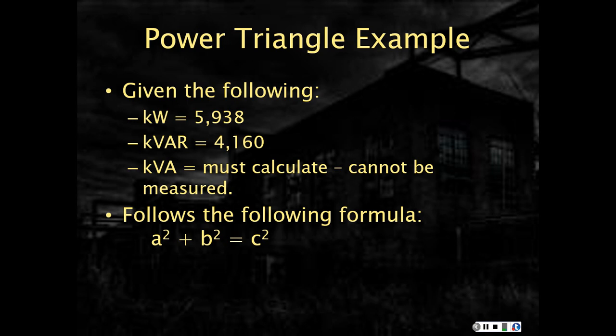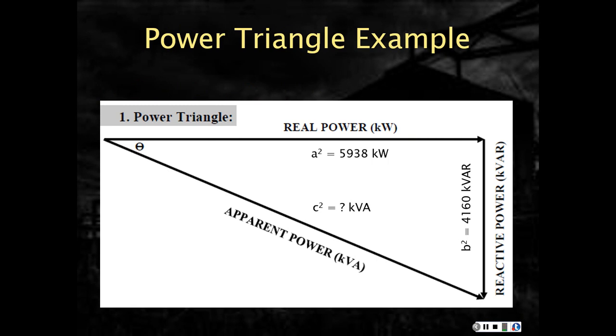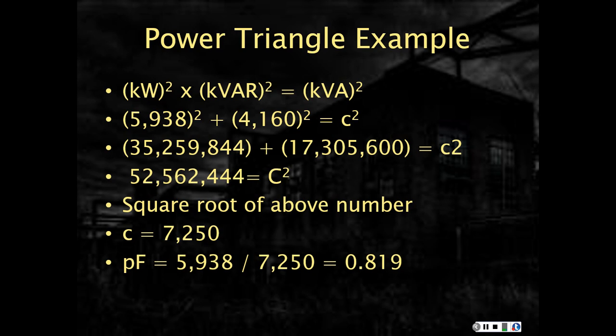So if we look at this, we can actually solve for the hypotenuse using the Pythagorean theorem, or a squared plus b squared equals c squared. If we look at the numbers from the previous example, we can solve for c, which should give us the apparent power. What you see here on this slide is the math that we go through to come up with the value of the kVA, which in this case was 7,250. Now, once we have that, we can take the real or working power, divide by the kVA, and get the power factor for this particular situation, which in this case is 0.819. As you remember from our previous discussion, this is borderline acceptable to most utility companies. Once we approach 0.8, the power company is going to start charging an extra penalty for a poor power factor.